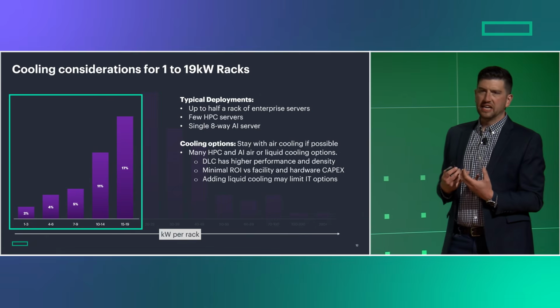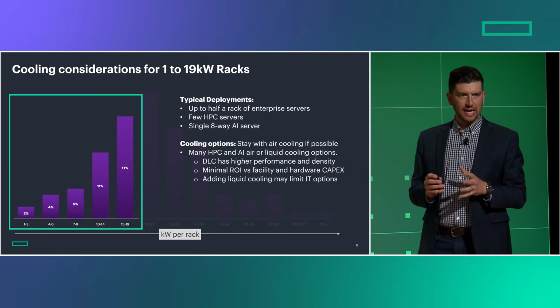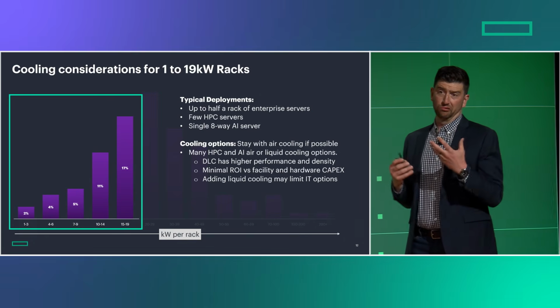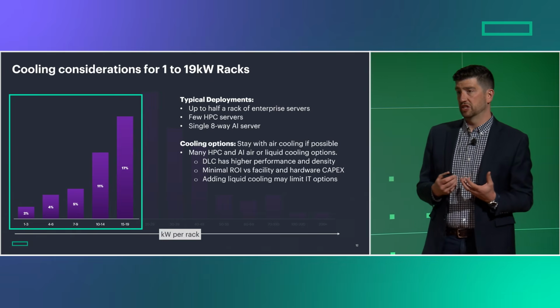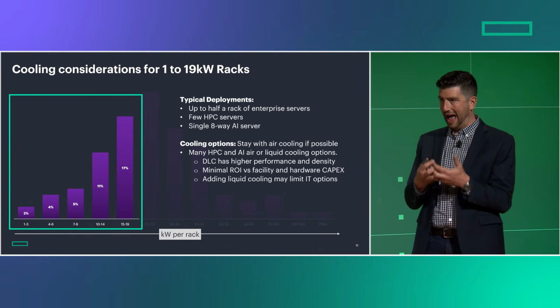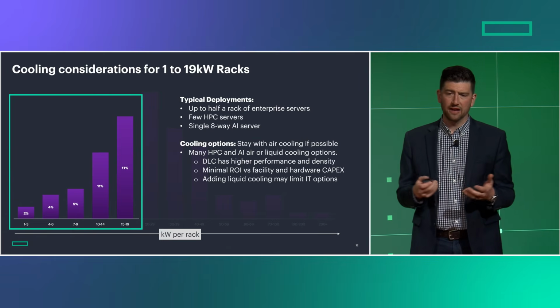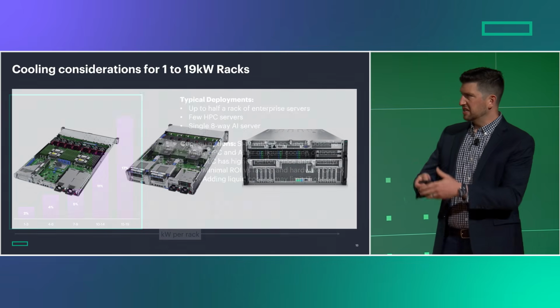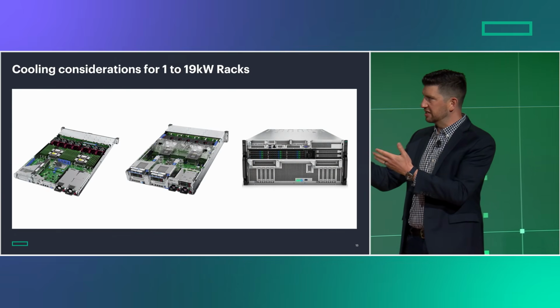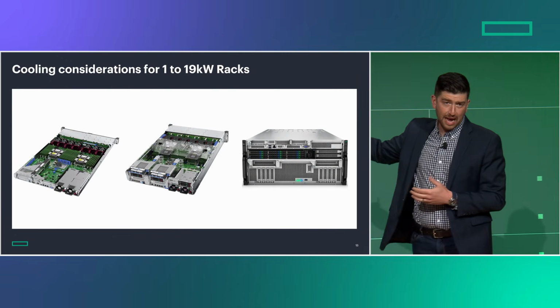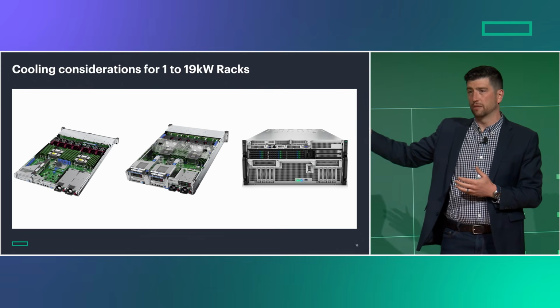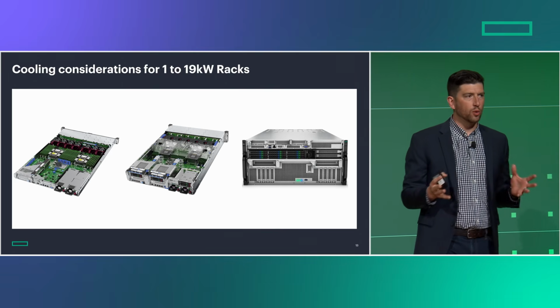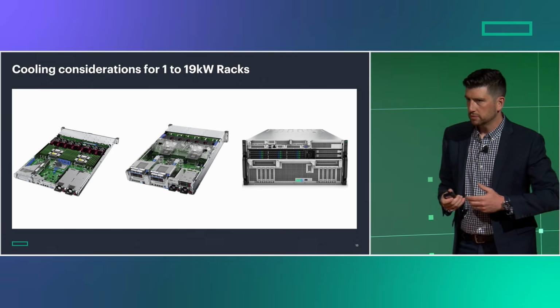If you have racks in the data center that are 20 kilowatts or less, an optimal strategy is really how can you increase the energy efficiency of the infrastructure you have. Pursuing liquid cooling is going to have some OpEx costs. This is pretty typical—a handful of ProLiant servers, maybe one of these AI boxes. These can be about 10 kilowatts a box, but those almost always are going to have an air-cooled option.